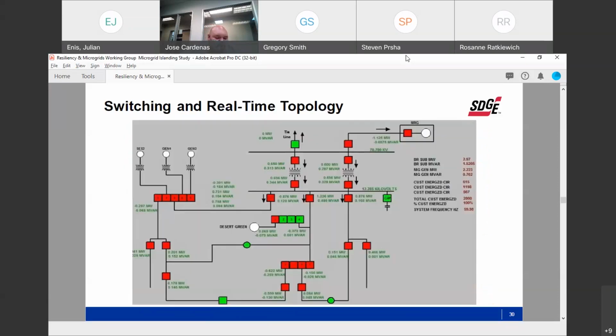One thing I almost forgot to mention is that, as part of our protection, we have multiple protection groups. We have a protection group for when you're grid connected, to protect the system. When you're grid connected, you have high inertia and a lot of fault current available for the relays. In a microgrid situation, you don't have that. You're in a low inertia system. So we have multiple relay protection settings that automatically switch groups when we go into an island.